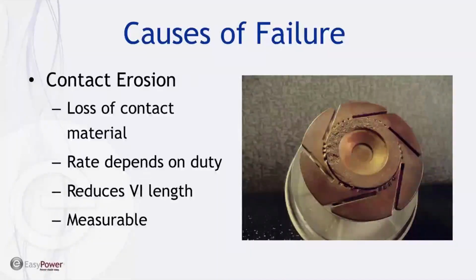So there are several causes of vac interrupter failure. The most prevalent is contact erosion. Over time, as you interrupt current, a small amount of the contact material is vaporized. For normal rated current, this is a very slow process. You should be able to operate for the whole life of the vac interrupter, which is generally between 10,000 and 30,000 operations before reaching the end of life at normal rated currents.